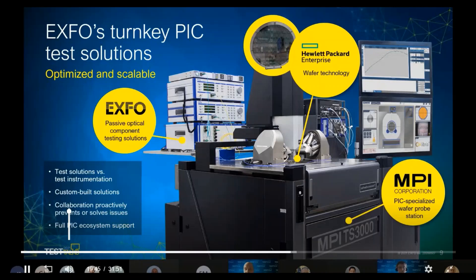On the two screens: the lower screen is for operating the probe station during setup, and for automation we can completely remote-control the probe station and measurement instruments. On the upper screen, the results are displayed — in this case an IL measurement sweep stepping from device to device. To automate this, we have the ability to use Python scripts, but we also came up with a nice solution with a test executive developed collaboratively with our partners, now available for optical setup measurements.